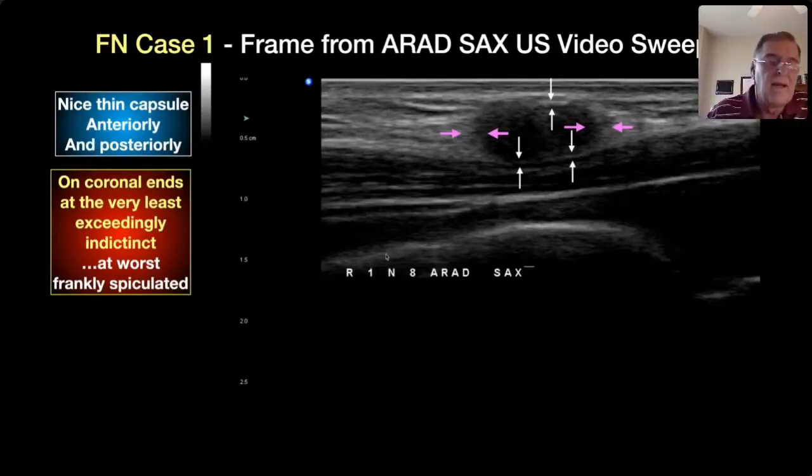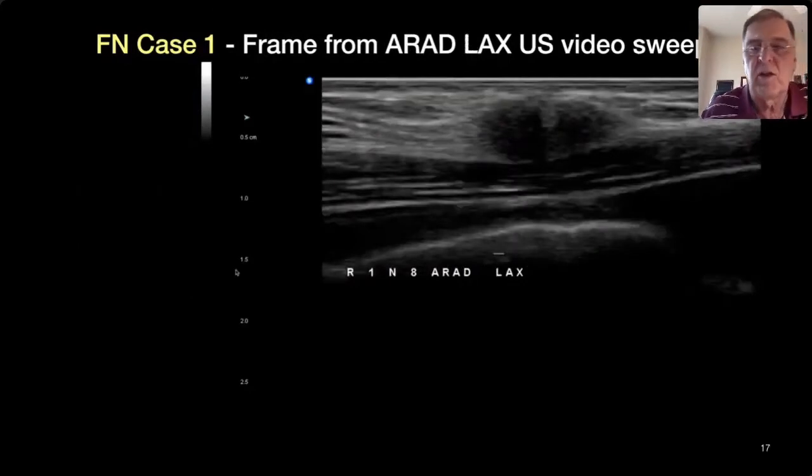What's the problem there? Well, axial resolution of ultrasound is about 100 microns. Lateral resolution of ultrasound is 500 to 1,000 microns. So we have much better resolution of the capsule in the front and back, because that requires axial resolution at high frequency, whereas showing the capsule on the sides requires a lateral resolution, which is lower. And also we have critical angle phenomena. As the beam comes down, it reflects and refracts off these sides. So we actually have to manipulate the probe. We have to use spatial compounding. We have to do whatever trick we have available to try to show the capsule on the ends as well as possible.